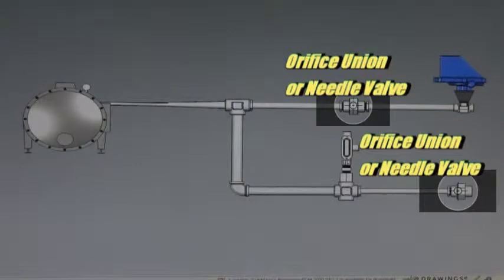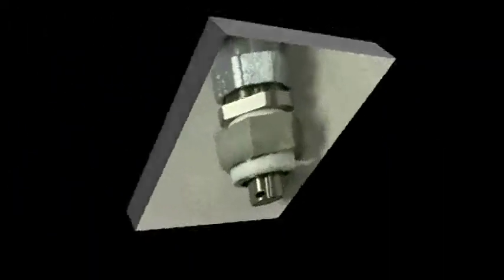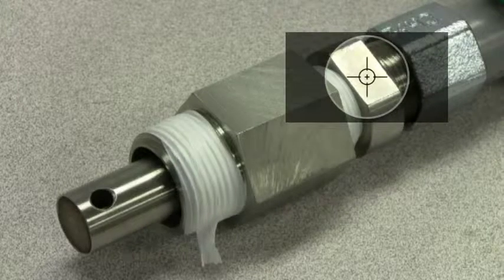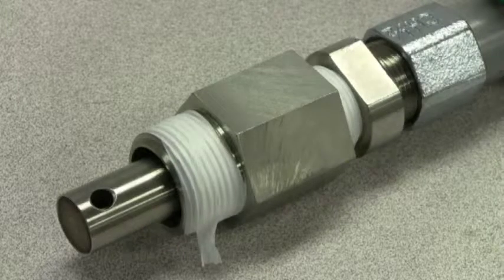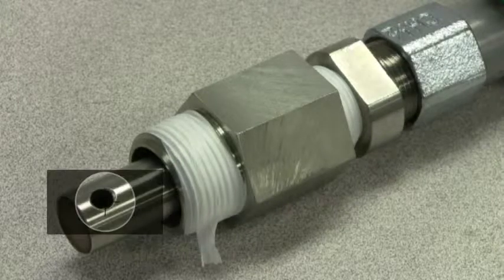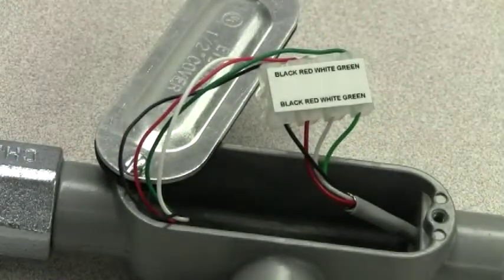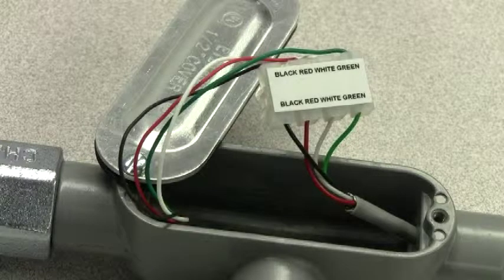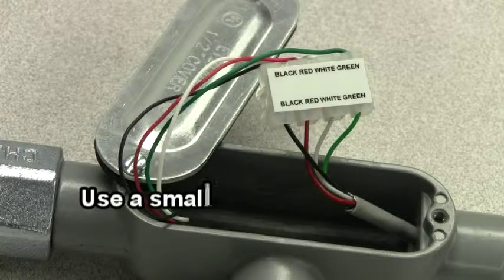When working with orifice unions, make sure the proper orifice plate is installed in the union. Install the sensor into the cross and then align the 2 flats so that they are perpendicular to the pipe. This will ensure the sample flows through the opening at the tip of the sensor. Inside the conduit box on the sensor, there is a terminal block that identifies the color code of the wiring.